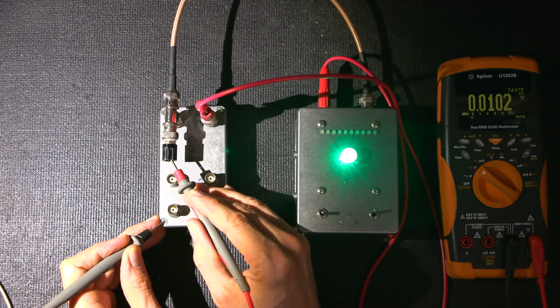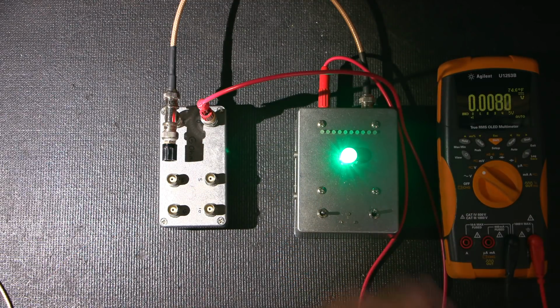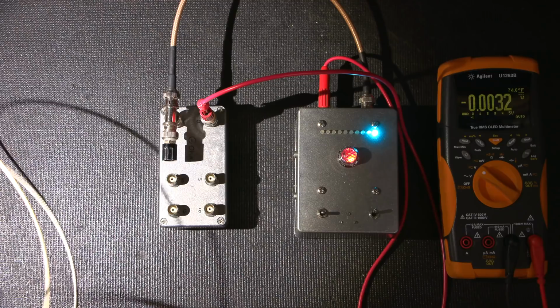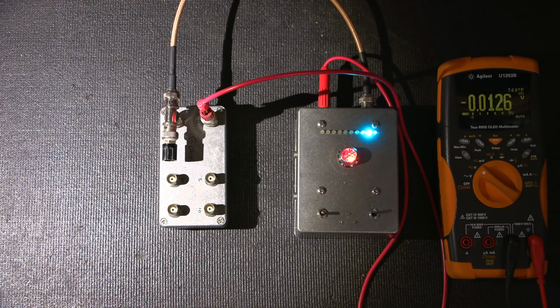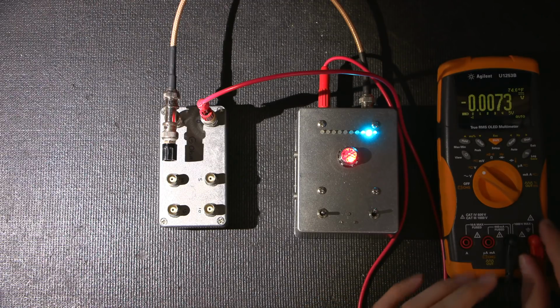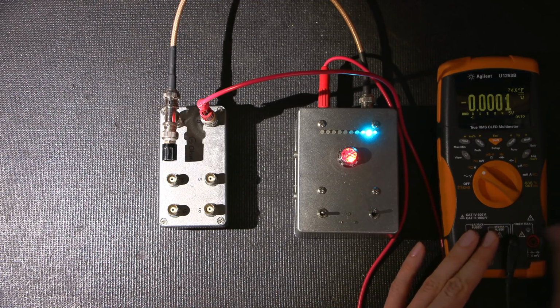Now you can see the reading that I have there. 0.01 of a volt DC. And I can keep this here indefinitely and it won't move, right? Because really this is skewing the results. And most meters will do this. So it's one way or the other. So, 40 gig ohms is much, much higher than the factory specs. Just move this cable here. Much higher than the factory specs for the input resistance on any of these types of meters, right?